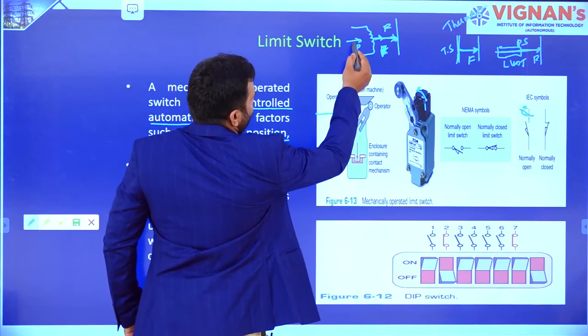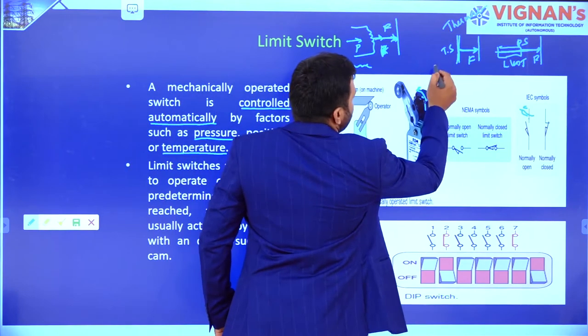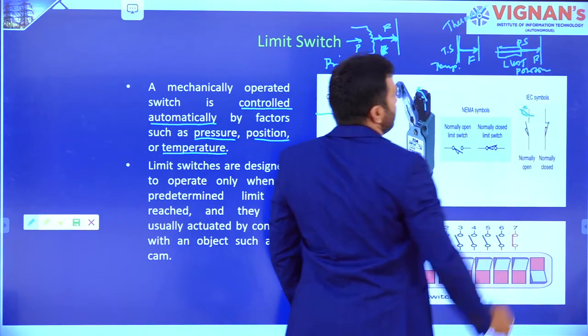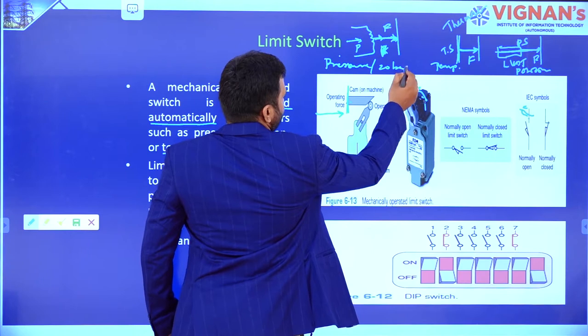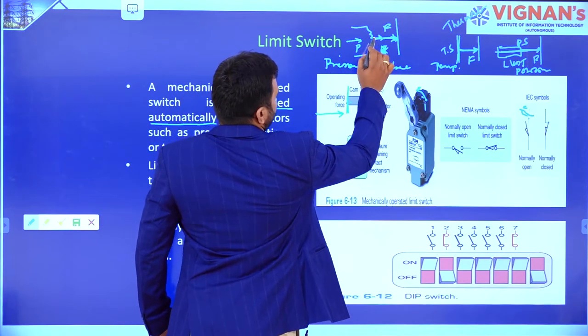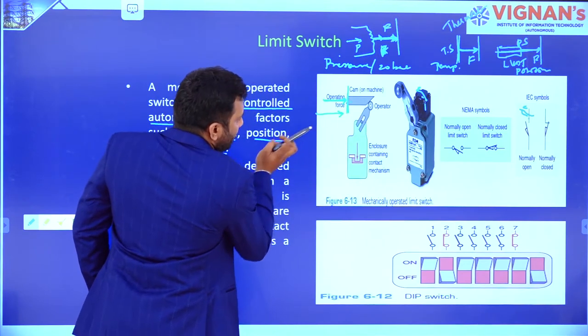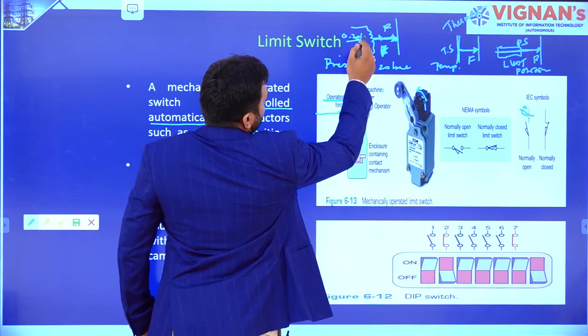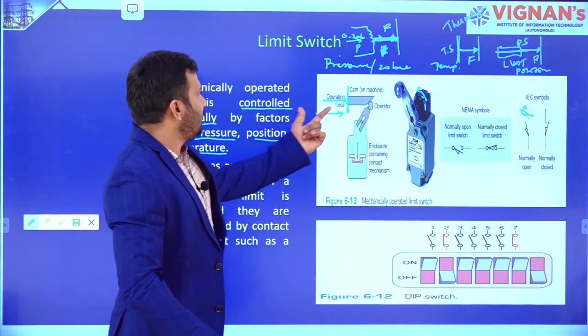A limit switch is where you set some limit for pressure, some temperature limit, and some position limit. Whenever you cross this particular pressure — for example, 20 bar pressure as a limit — whenever it reaches 20 bar, this is going to give input force on this particular terminal, that means on this particular cam. The input force is going to vary with pressure acting on this particular bellow. So as pressure increases from 0 bar to 20 bar, the force is correspondingly acting on this particular cam, the actuating device.